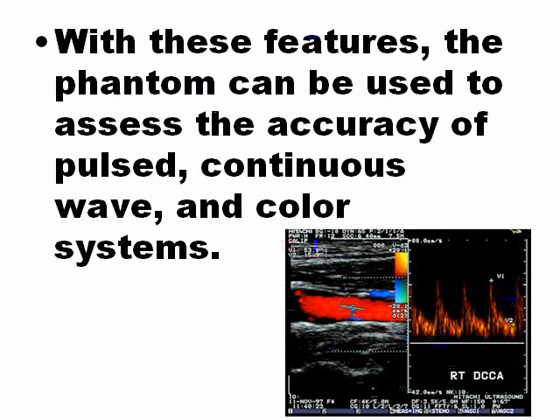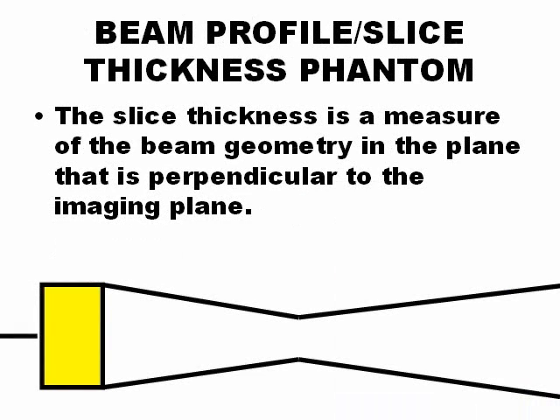and continuous wave and also color Doppler system. Beam profile, slice thickness phantom. The slice thickness phantom is to measure the dimension of the beam. Remember, the beam has 3 dimensions, and the lateral and elevational resolution are hard to measure, and we are using the beam profile slice thickness to know what the thickness of the beam is.